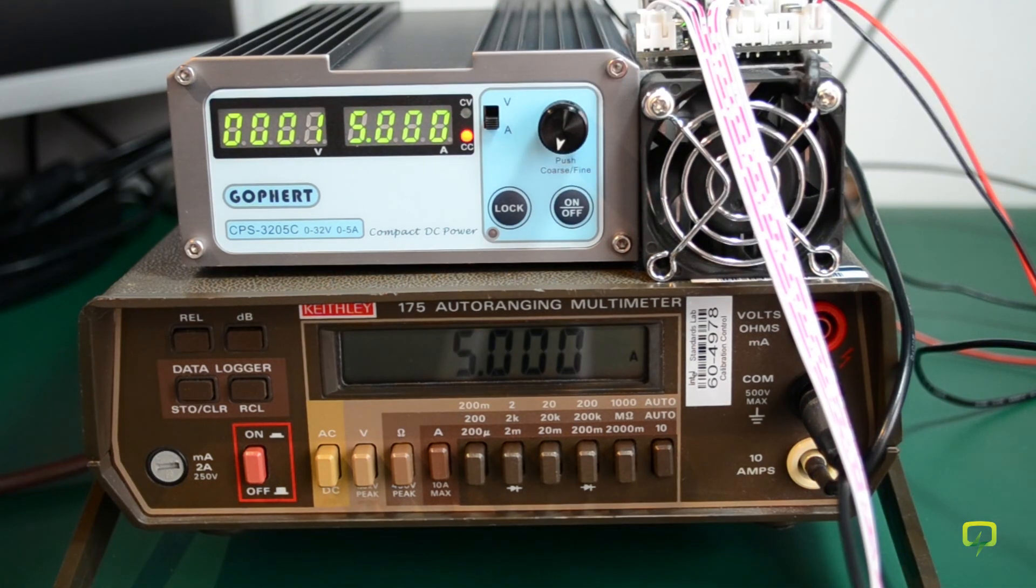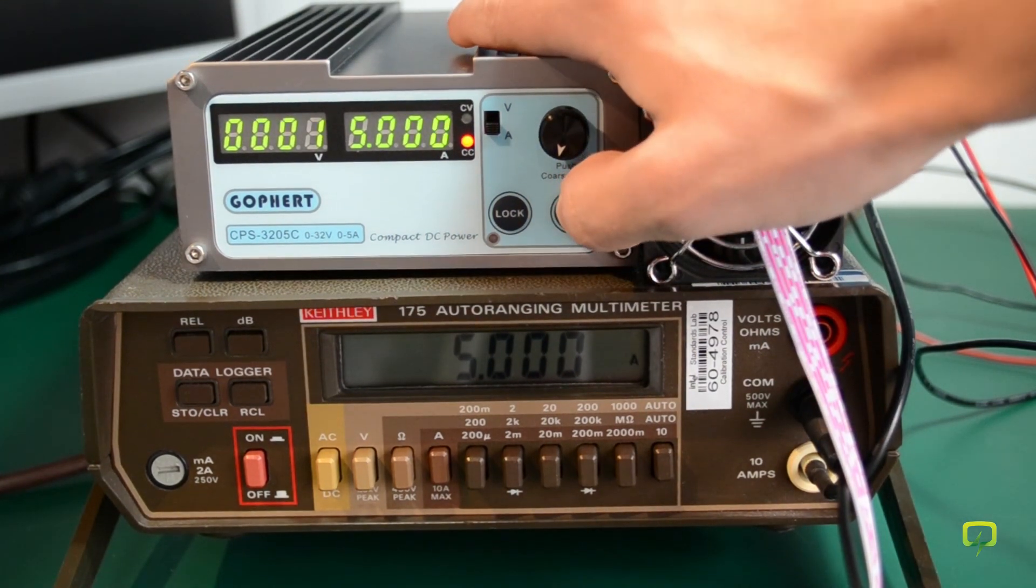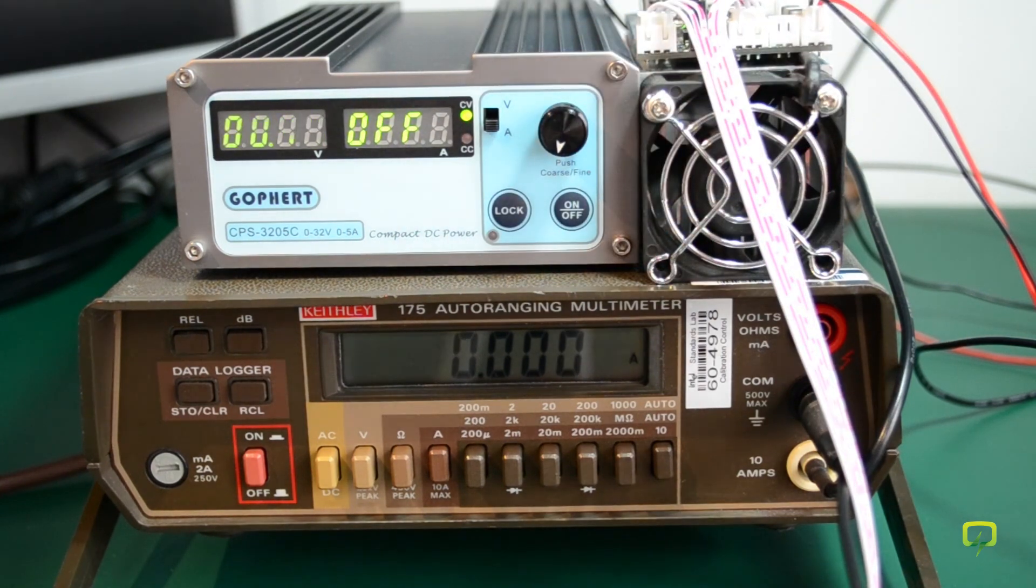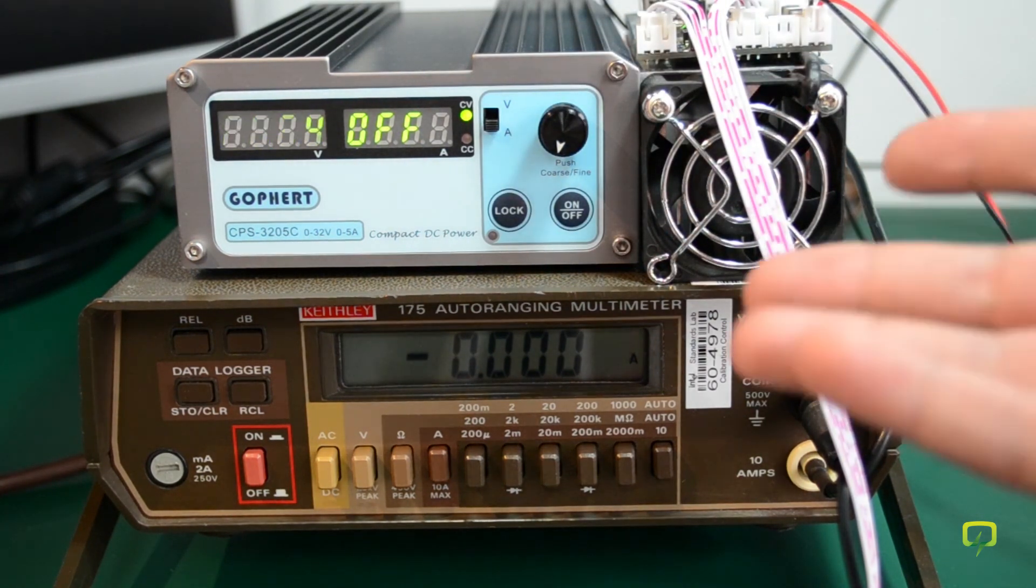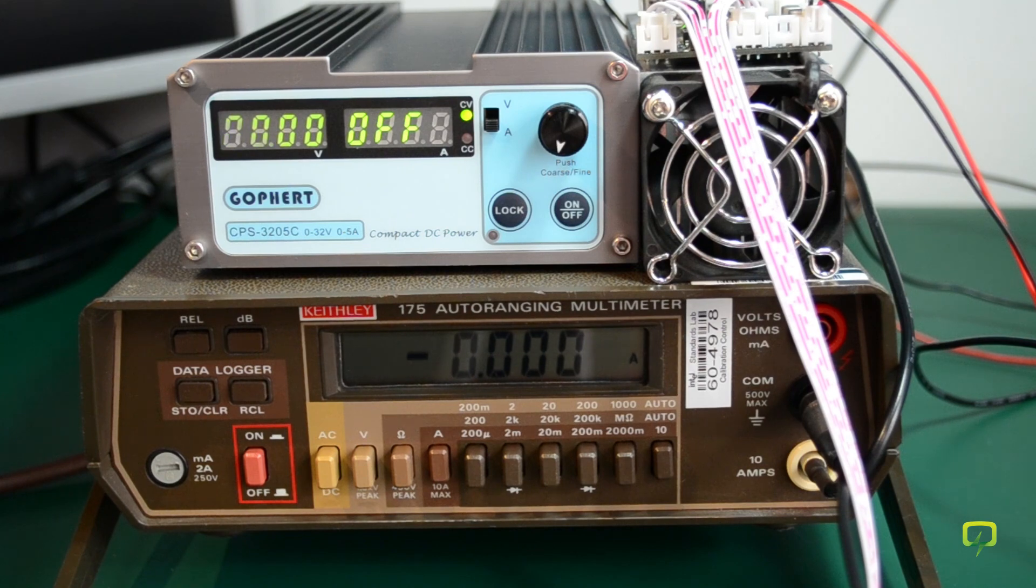Okay. And now I have to press the on/off button once again to complete the calibration. Okay. And the power supply automatically exited the calibration procedure and turned its output off. I will post the entire procedure in the description of this video.